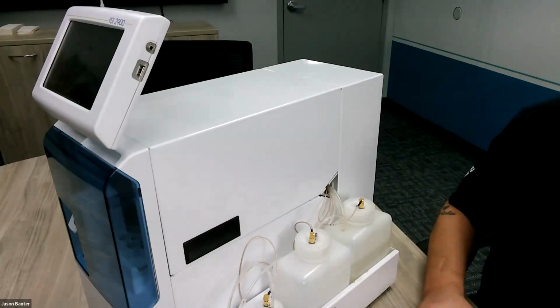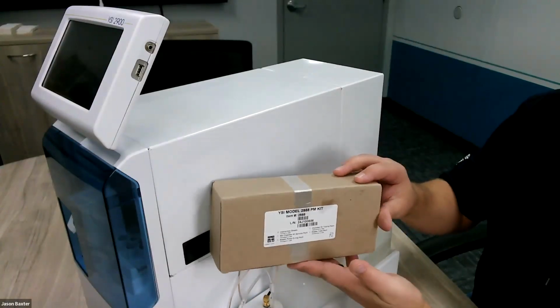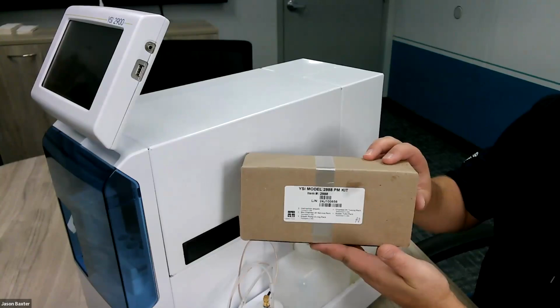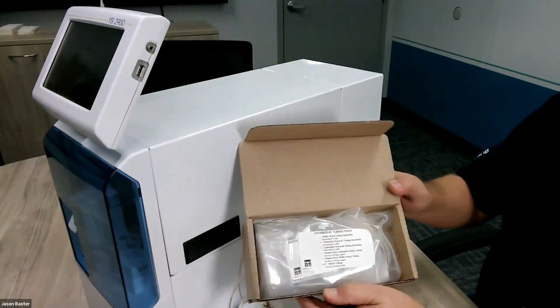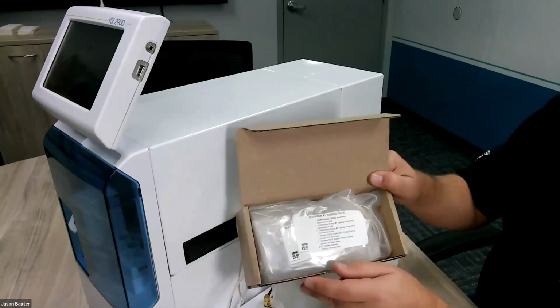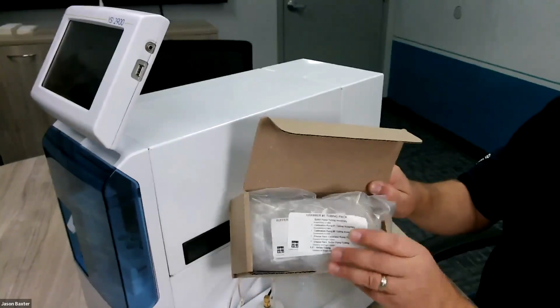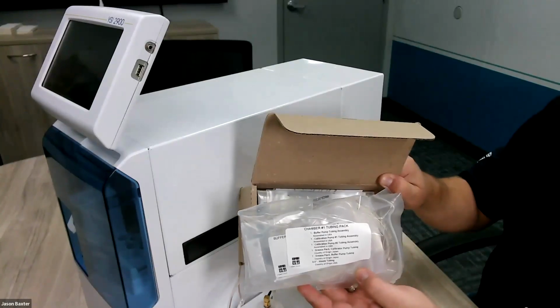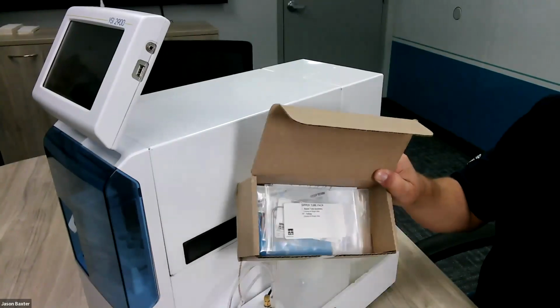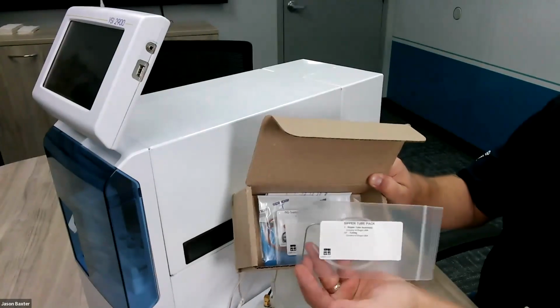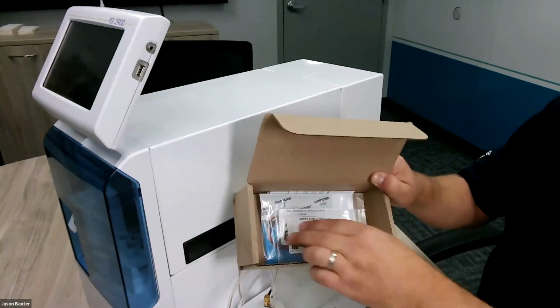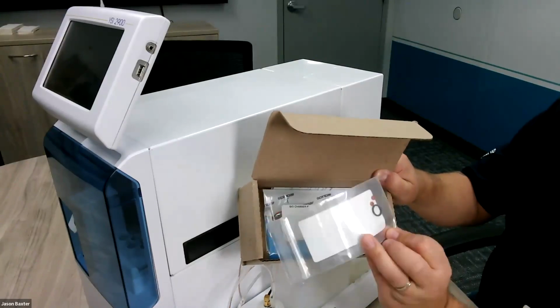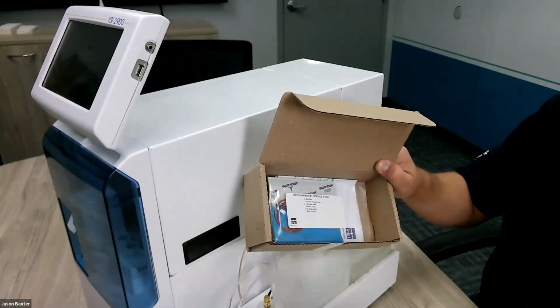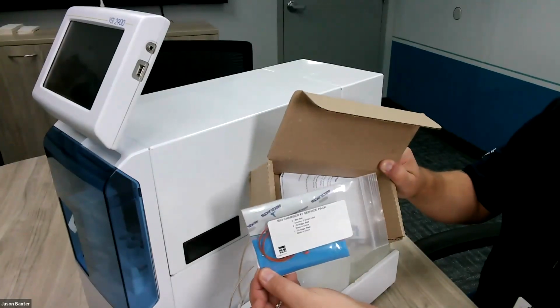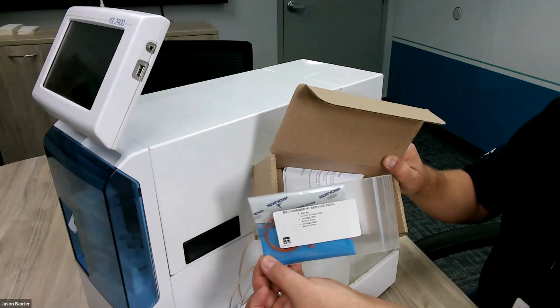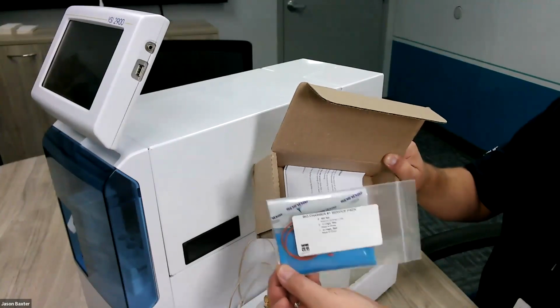So when it's time to do your PM kit, you're going to buy the entire PM kit. It's going to come in a box. Inside of the box will be a multitude of Ziploc bags, each containing its own label. There will be one large bag that will show chamber 1 tubing pack, which we'll get to in a little while. There will also be an individual bag that contains the sample needle. There will be another individual bag that contains the sipper pump O-rings. And lastly, there will be a bag that will say biochamber number 1. This contains all the O-rings and the stir bar for your sample chamber.